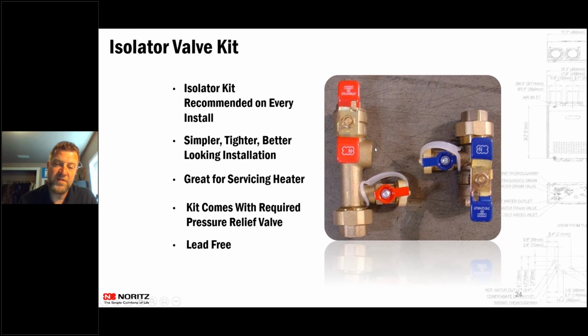So with tankless, it's just a pressure relief valve. It's not a temperature and pressure relief valve, because we are not storing any water. We don't have to have the temperature side of it, because we're not going to store and make hot water. With tankless too, you do not need an expansion tank when installing a tankless water heater.